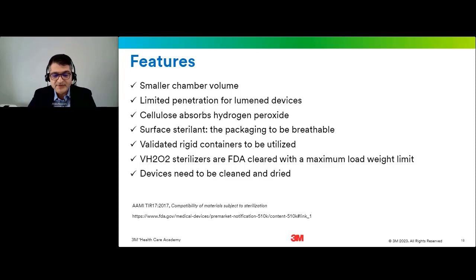Also, we mentioned in the previous slide that it is a surface sterilant, so it means that the packaging needs to be breathable. It needs to have a breathable layer such as Tyvek. Only rigid sterilization containers that are validated and FDA cleared for hydrogen peroxide processes should be utilized. Maximum load limit is also very important. Depending on the manufacturer, you choose the cycle, and then it has weight limits. And even which shelf to use, upper shelf or bottom shelf, or both of them, varies based on which cycle type you use. So it is very important to follow the manufacturer's instruction for use and the limitations.